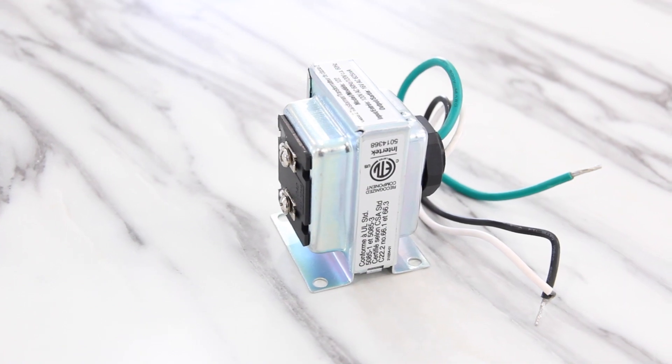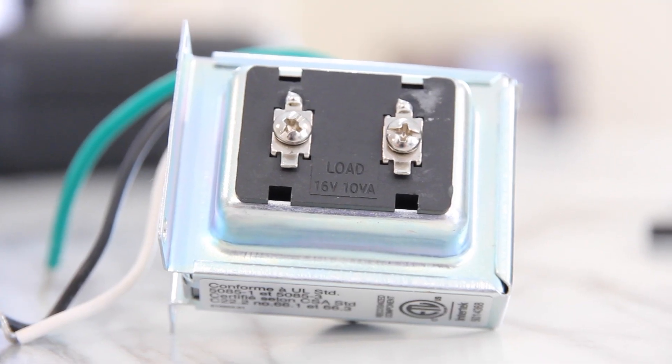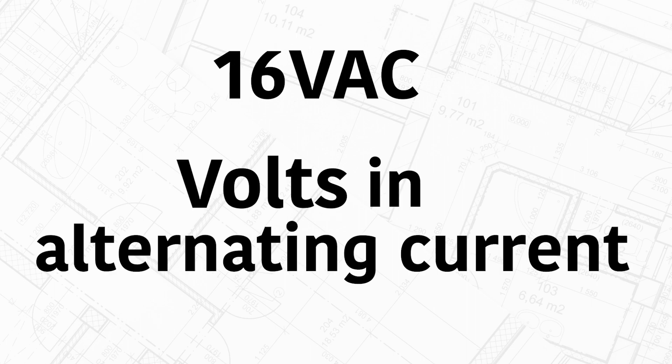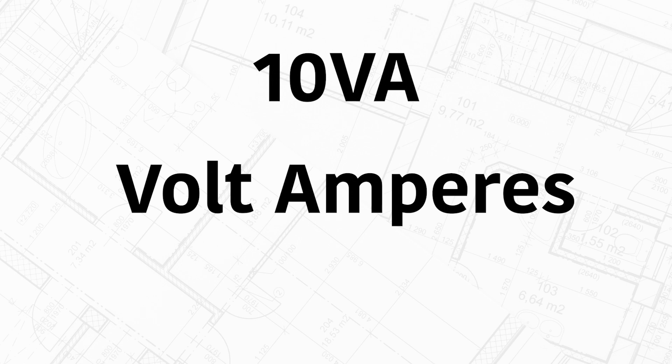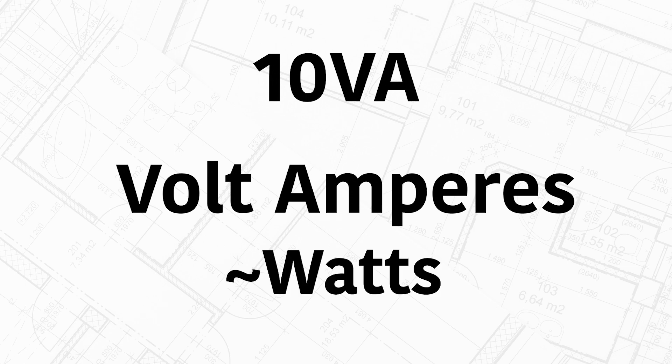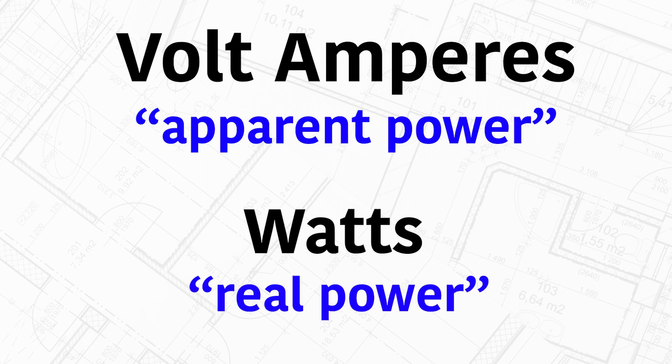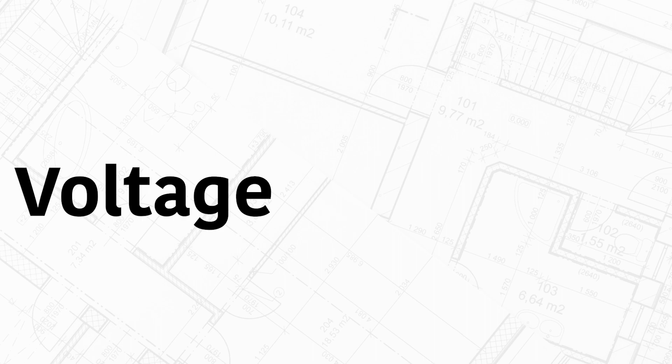There are two main numbers on a transformer. The first is voltage — this one is 16VAC, which stands for volts in alternating current. The second number is 10VA, which stands for volt amperes, loosely equivalent to watts. Technically, volt ampere refers to apparent power and watts are the real power — both are simply voltage multiplied by amperage. If that sounds too technical, don't worry; we are basically just matching numbers here.